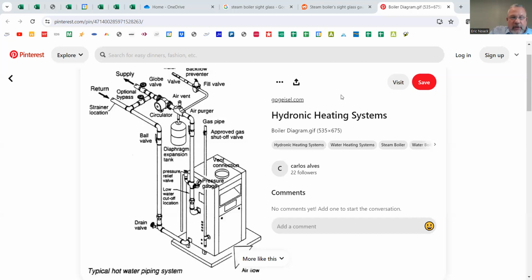Okay. So then underneath that air vent, you can see that tank, and that's an expansion tank. And what I talked about before, when the water cools, it shrinks. That expansion tank has a diaphragm in the bottom of it, a rubber diaphragm that's charged to 12 psi, and it makes its way up. It pushes that water as it shrinks to make sure that no air accumulates in there. When the water heats up, it pushes that diaphragm back down as it expands. So essentially, it's an adjustment that'll help make sure that that water stays completely full and that air doesn't get reintroduced into the system. So that's a lot. Any questions on what I've talked about so far?